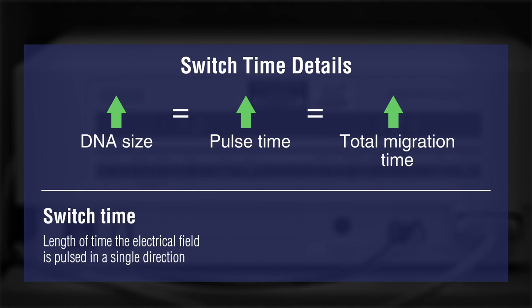The switch time is the length of time that the electrical field is pulsed in a single direction. For example, a 10 second switch time means that the electrical field will be pulsed in one direction for 10 seconds and then switched to another direction for 10 seconds.